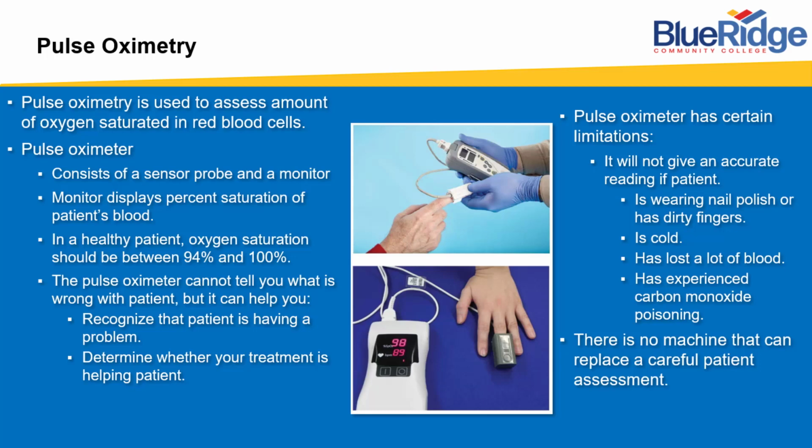You want to place the sensor probe, or the little light that's inside the probe, directly over the patient's fingernail bed or fingertip, or their earlobe if you have that type of probe.